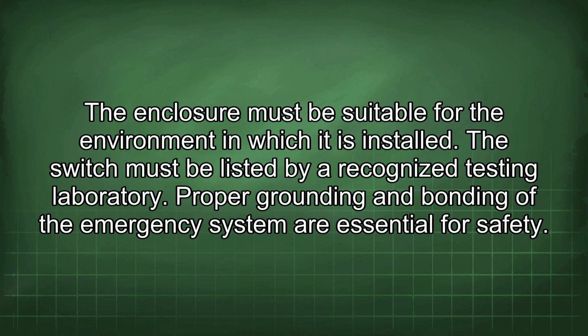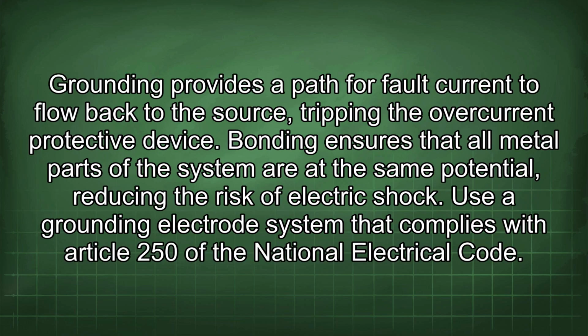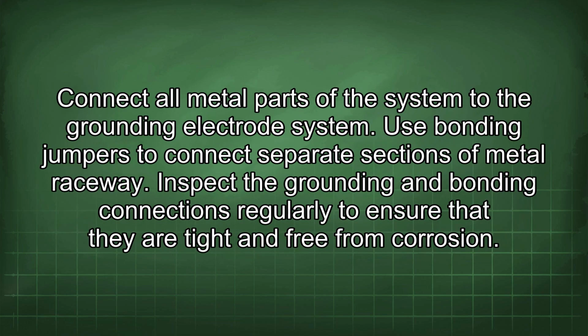Proper grounding and bonding of the emergency system are essential for safety. Grounding provides a path for fault current to flow back to the source, tripping the overcurrent protective device. Bonding ensures that all metal parts of the system are at the same potential, reducing the risk of electric shock. Use a grounding electrode system that complies with Article 250 of the National Electrical Code. Connect all metal parts of the system to the grounding electrode system. Use bonding jumpers to connect separate sections of metal raceway. Inspect the grounding and bonding connections regularly to ensure that they are tight and free from corrosion.